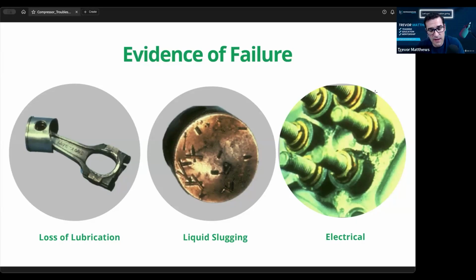It's all about facts. When you have all those numbers, even if you're not that great at figuring out what's going on, if you give them to an expert and they're the right numbers, they can usually tell you what is going on with that system. They can tell you that you've got liquid in that compressor, or you're running your evaporator too high, or your condenser's not rejecting enough heat. Just by looking at the numbers, the more numbers, the better.